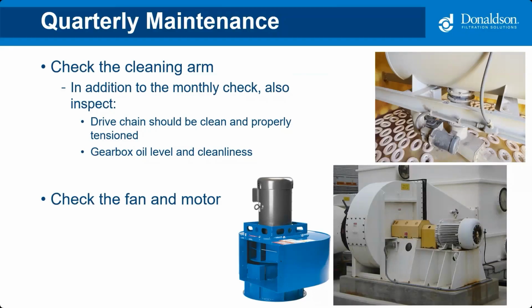Just confirm the drive chain is clean. It's properly tensioned. It hasn't gotten loose over time. The gearbox in there for that. Just check the oil level. Make sure it's still at the right level and that the oil is clean and doesn't need replaced. Again, if that oil starts to get really dirty, you're going to want to replace that.